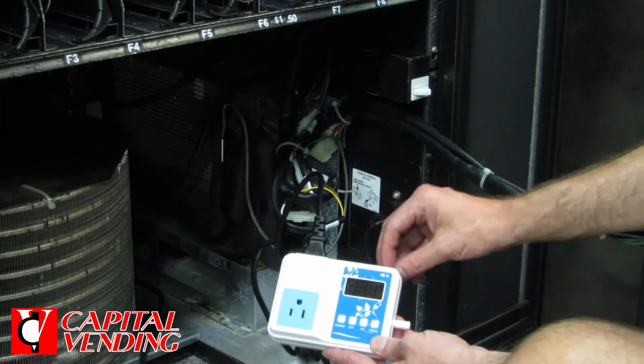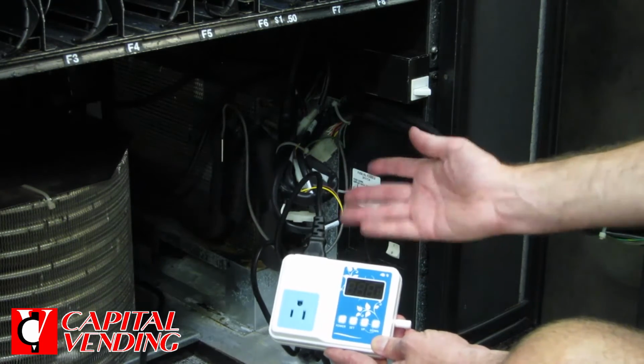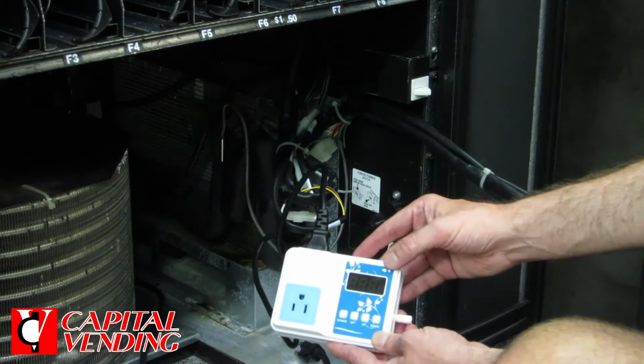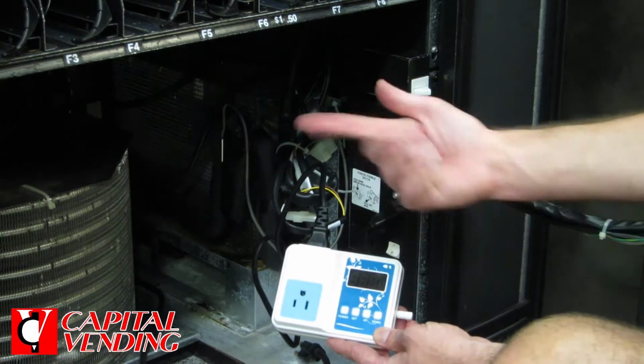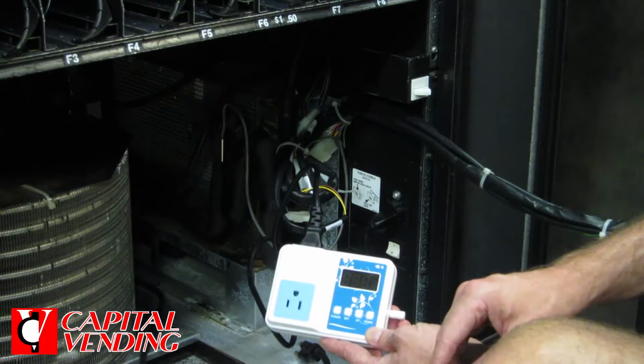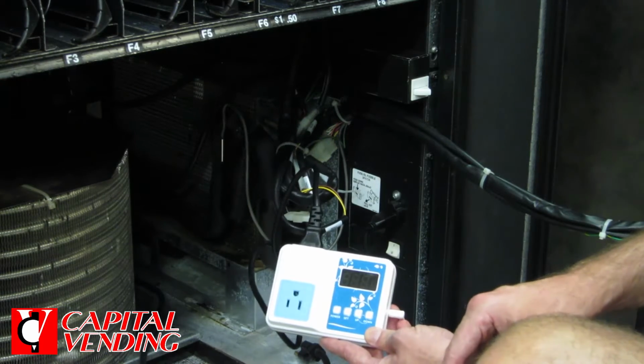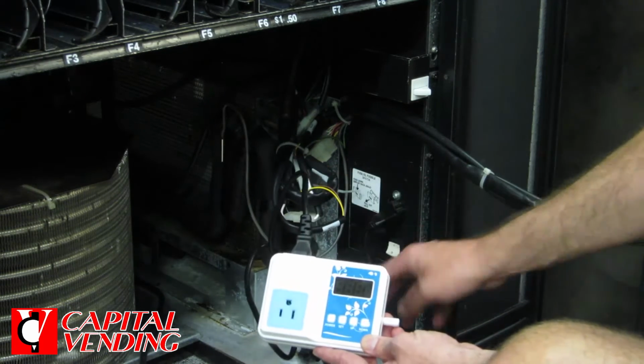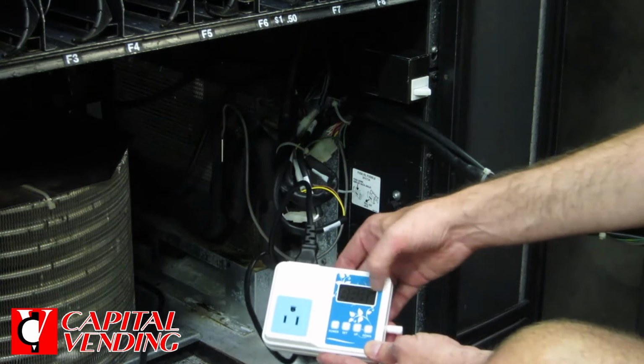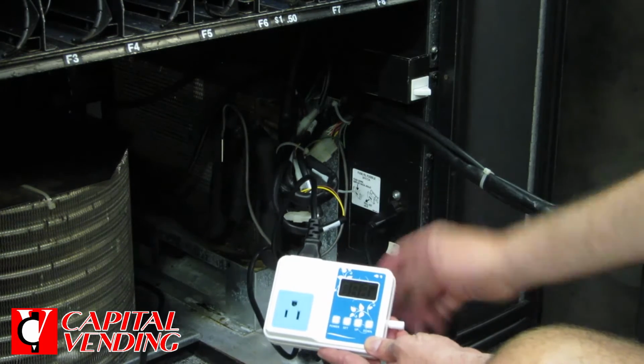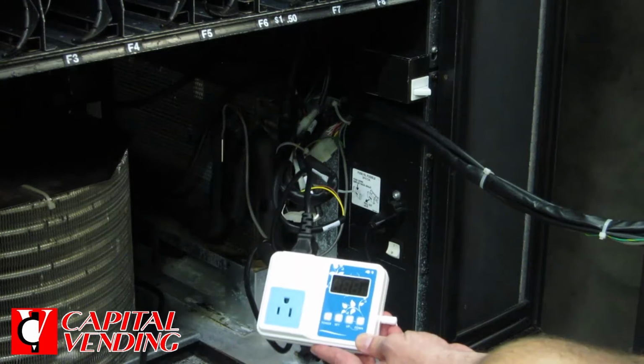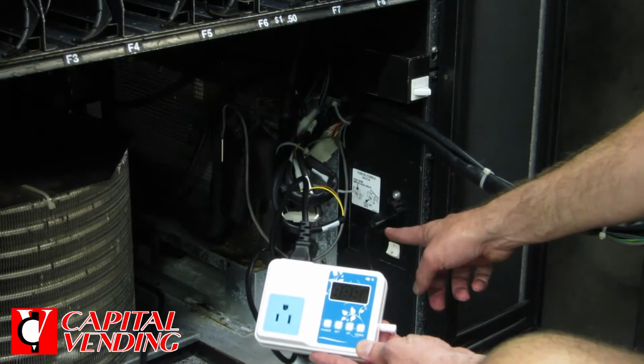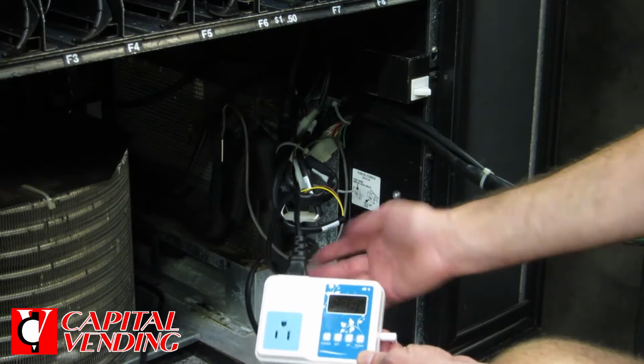When this machine is closed, the control board sometimes waits up to 5 or 10 minutes to turn on the refrigeration system so it doesn't damage the compressor. So if you plug this in and don't get power, that helps with troubleshooting — it could mean the board is bad, or a door switch.